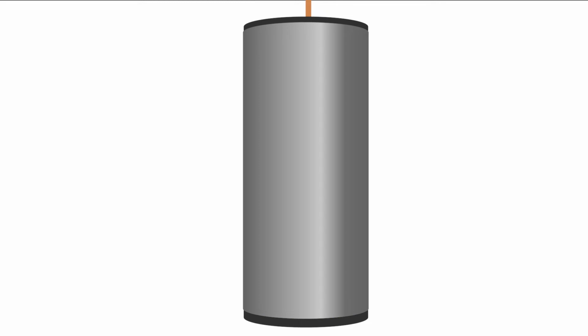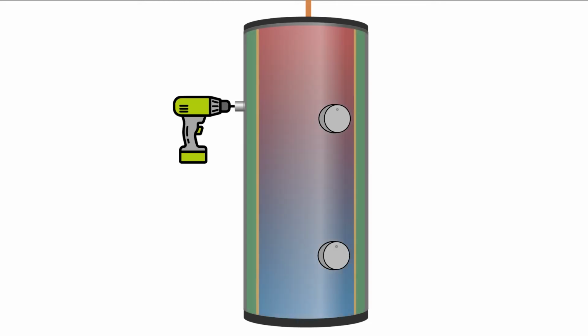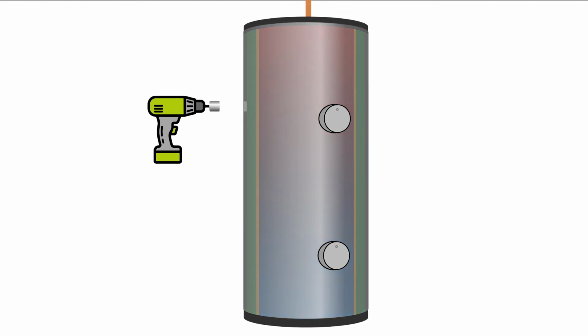If the tank has a steel or plastic jacket, use the hole saw to bore a 44mm hole. Be sure to only drill through the outer jacket. Stop when the outer jacket is cut. Remove the pilot drill from the hole saw and then turn it by hand to gently cut through the insulation on the tank wall. Stop when you feel the teeth of the saw touch the metal side of the internal tank. Remove and discard the insulation from the hole saw.